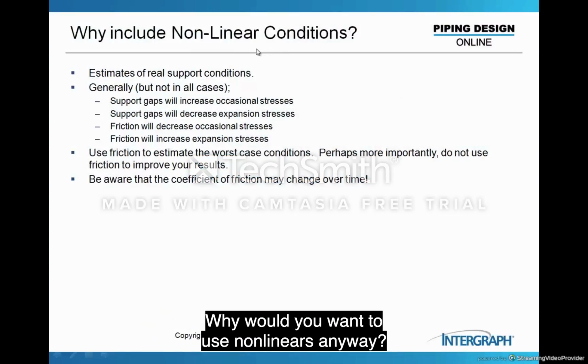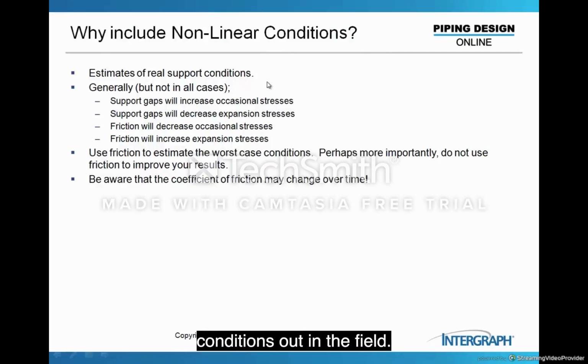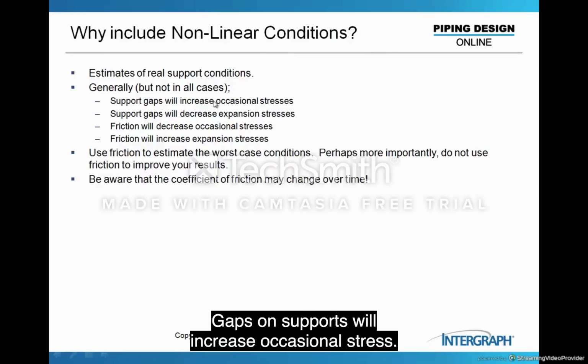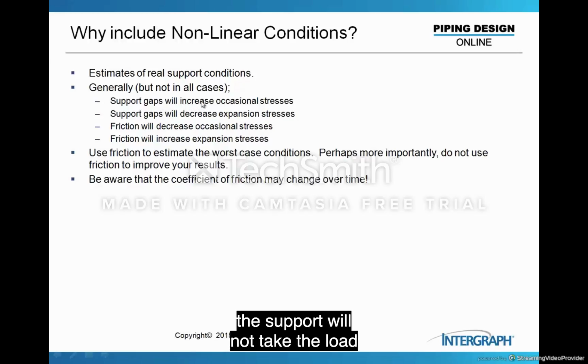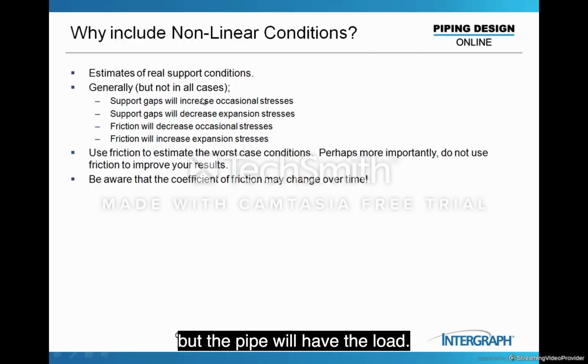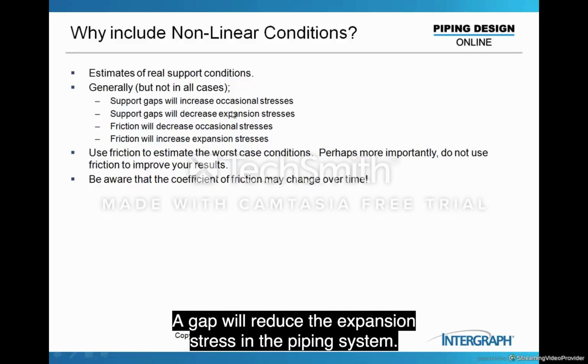Why would you want to use nonlinears anyway? Well, it gives you a better estimate of the real support conditions out in the field. Gaps on supports will increase occasional stress, because if the pipe does not come in contact with the support, the support will not take the load, but the pipe will have the load. The opposite happens with expansion stresses with gaps. A gap will reduce the expansion stress in the piping system.